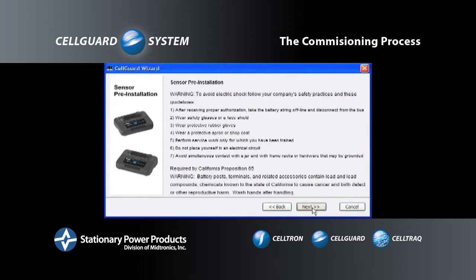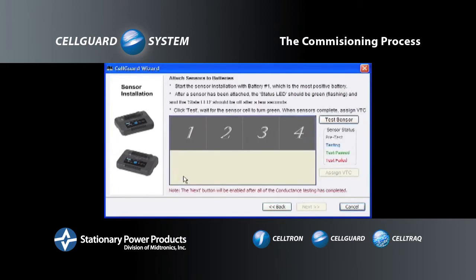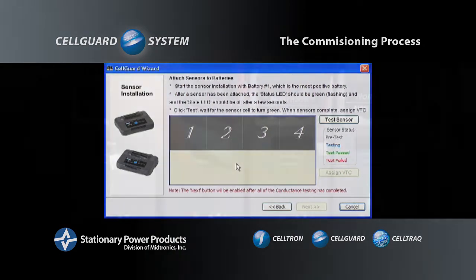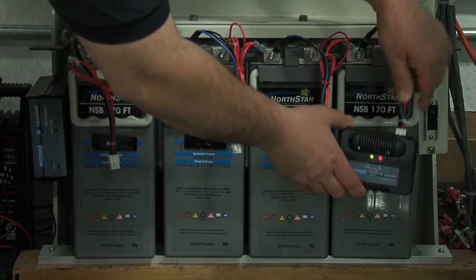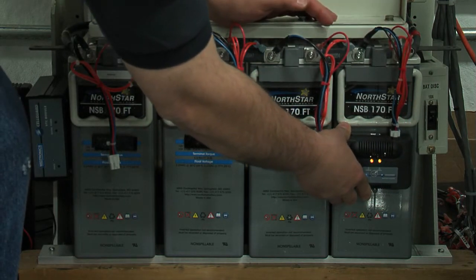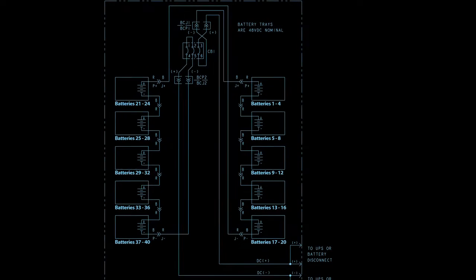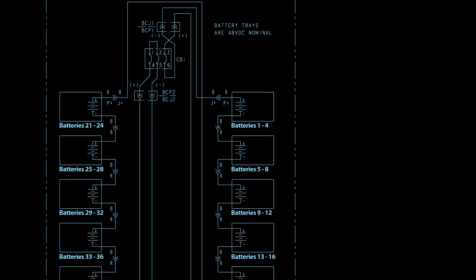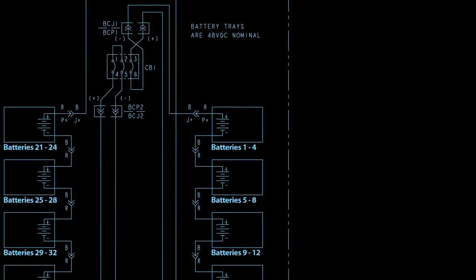Click Next. The Wizard makes a grid for the number of sensors you entered. If 40 sensors were entered, then the Wizard would have made a grid consisting of 40 squares on this screen. Since 4 was entered, the Wizard made a grid of 4 squares that represents the 4 sensors we are commissioning. Start by connecting the first sensor to the cable set coming off of battery number 1. For consistency, Midtronics recommends that the most positive battery in the string is battery number 1.